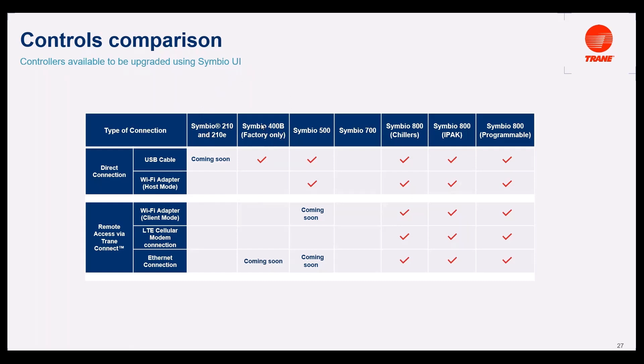For the 400B, you can now use the USB cable direct connection, and you will be able to do it using Ethernet connection in the next releases. For the 500, you are able to use the Symbio UI to upgrade the firmware using the USB cable, the Wi-Fi adapter in host mode. Through Trane Connect, you will be able to upgrade this controller using the Wi-Fi adapter in client mode. Ethernet connection for the 500 will also be available in the next releases.